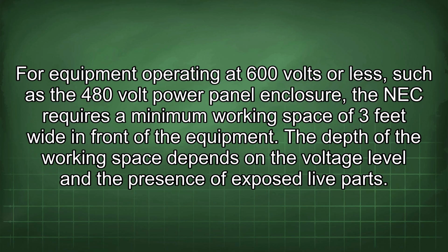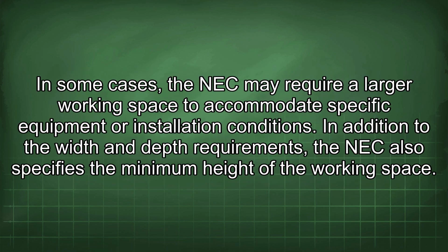For equipment operating at 600 volts or less, such as the 480-volt power panel enclosure, the NEC requires a minimum working space of 3 feet wide in front of the equipment. The depth of the working space depends on the voltage level and the presence of exposed live parts. In some cases, the NEC may require a larger working space to accommodate specific equipment or installation conditions.